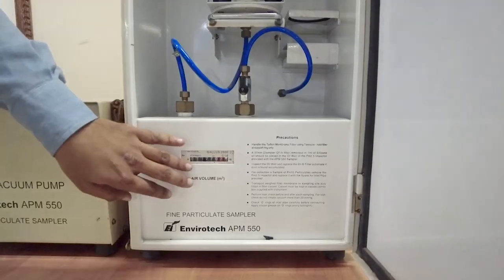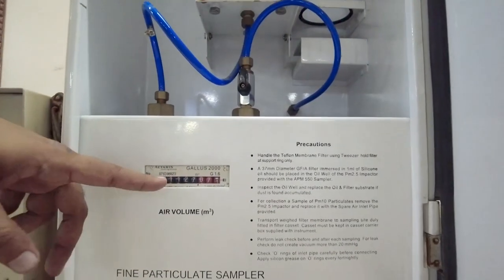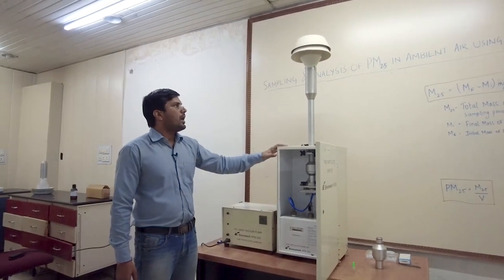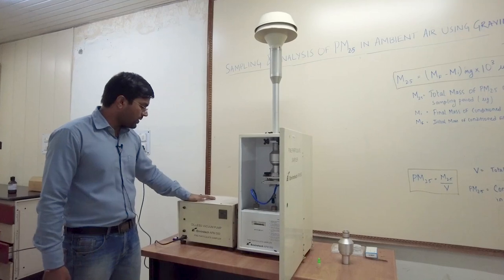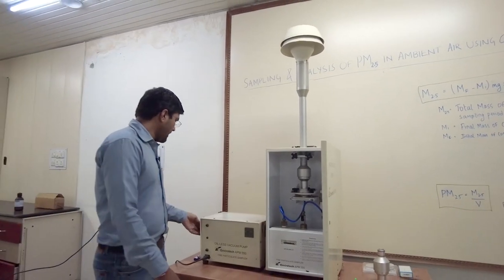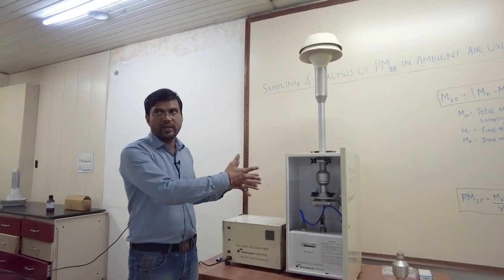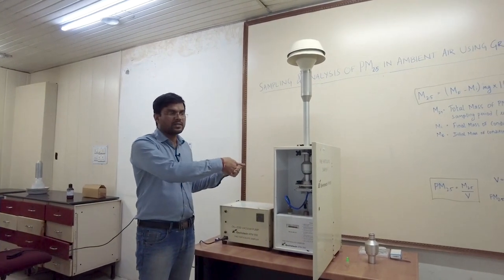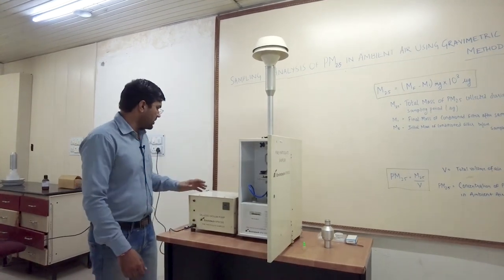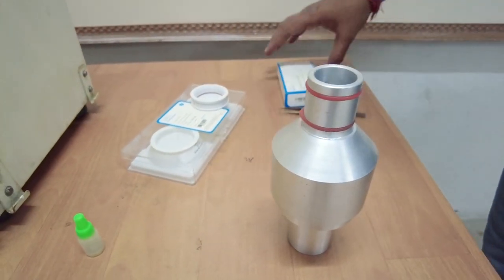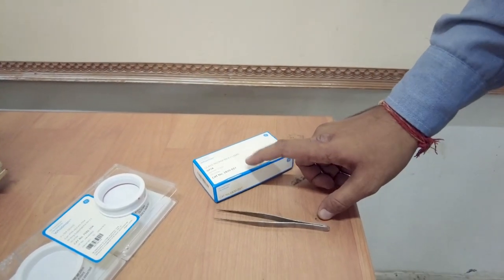Now, what happens inside the WINS impactor: here we have another unit of the WINS impactor. It contains the 47 mm PTFE filter and a GFA filter — a glass microfiber filter — for the impaction purpose. This is the WINS impactor; we gently open it when setting up the instrument. Inside the impactor assembly we have the oil well. We remove the upper part of the oil well, and inside we have a 37 mm GFA filter. Before starting the experiment we place this GFA filter.